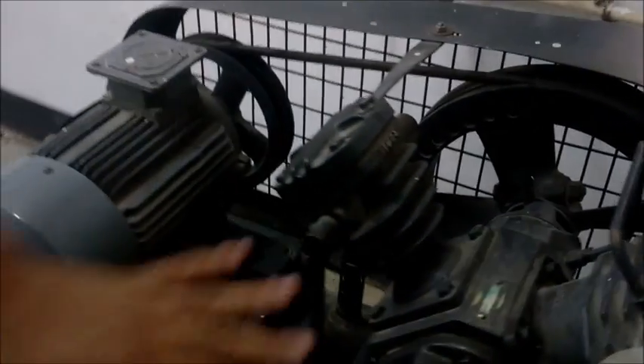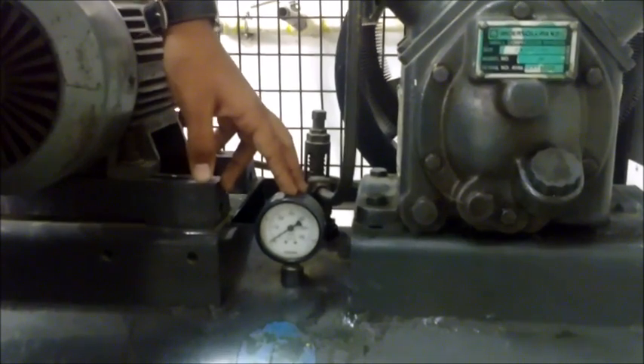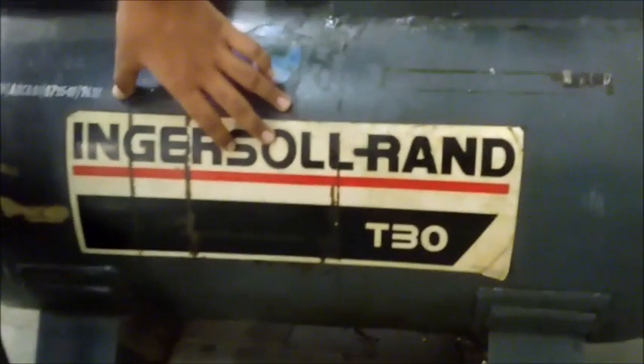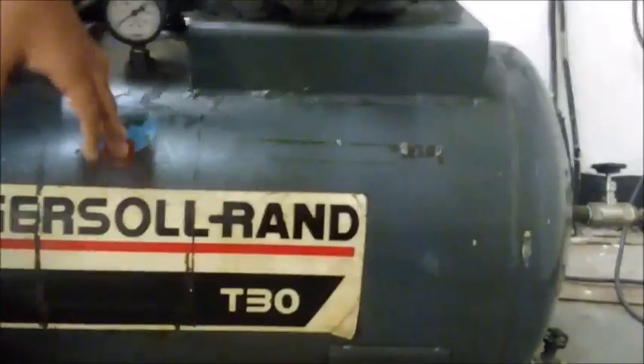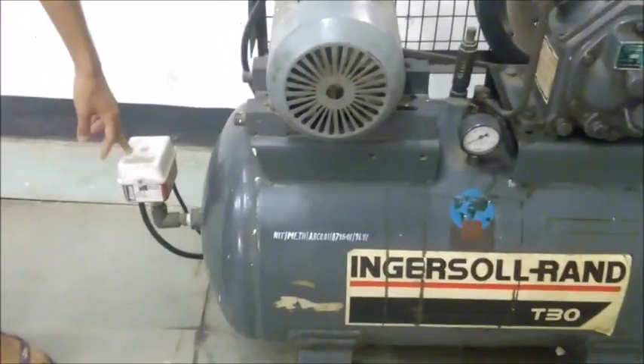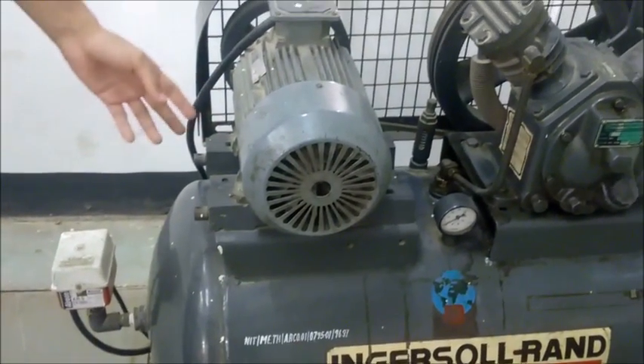Here, high-pressure compression takes place. This is the air filter where air gets sucked in. Between the two stages there is an intercooler with fins. This is the pressure gauge from which we have noted down the pressure. This is the storage tank of capacity 150 liters. This is the pressure control switch that opens the electrical contact of the compressor when a certain set pressure is reached.